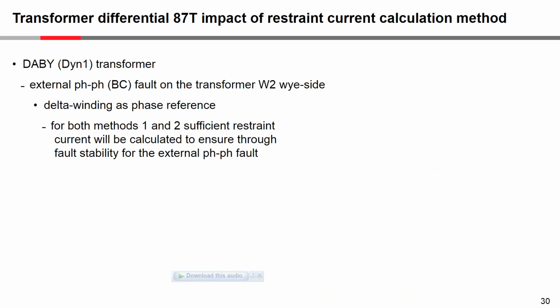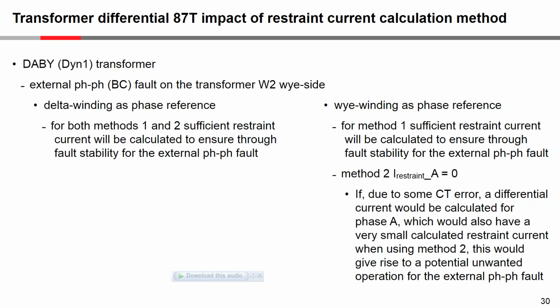But the problem is, what about method 2, where the restraint value for A phase was calculated theoretically as 0. So now, if due to some CT error a differential current would be calculated for phase A, which would also have a very small calculated restraint current, as we've seen, theoretically 0, when using method 2. So this could give a potential unwanted operation for the external phase-to-phase fault.